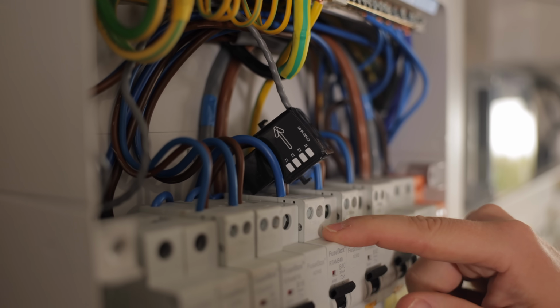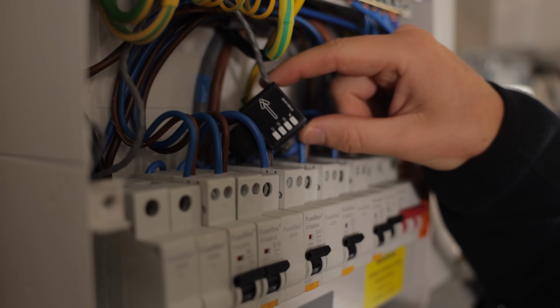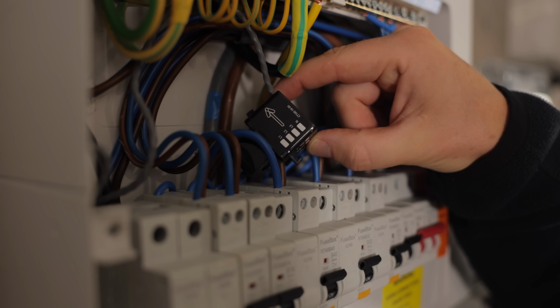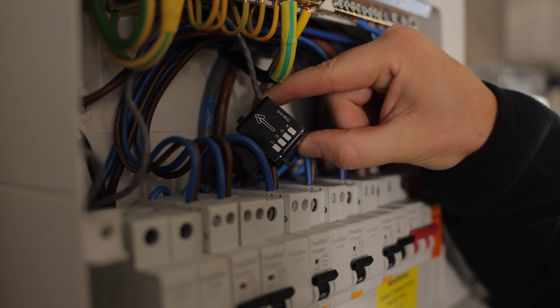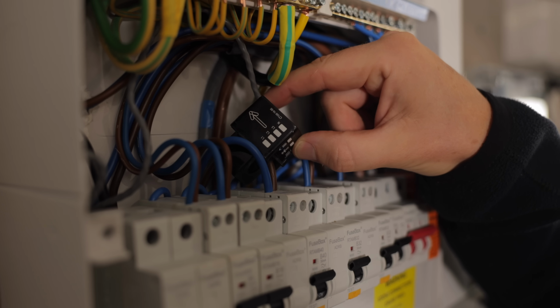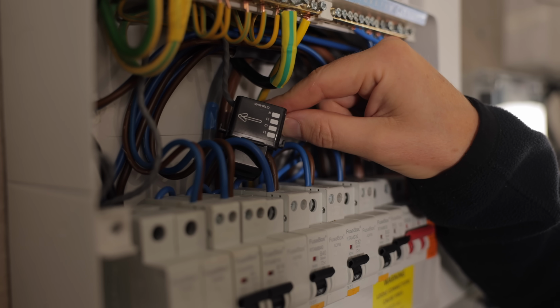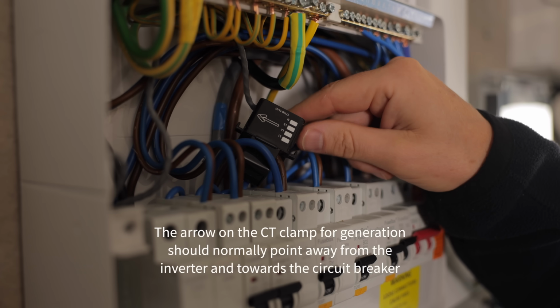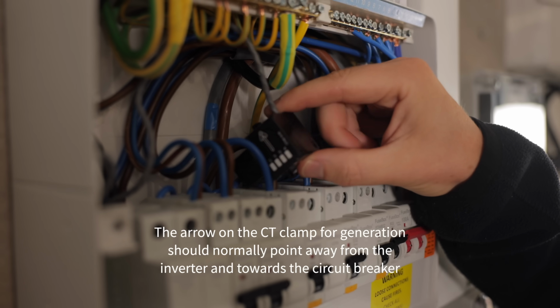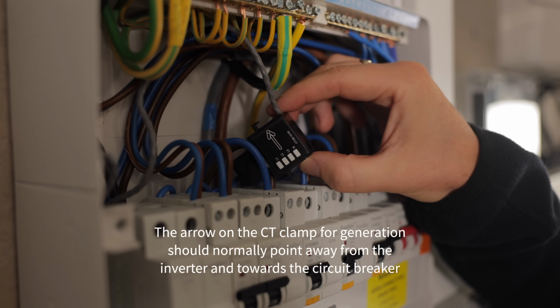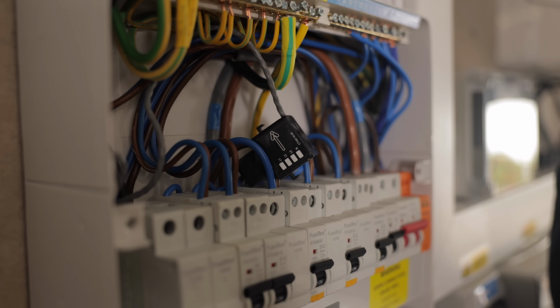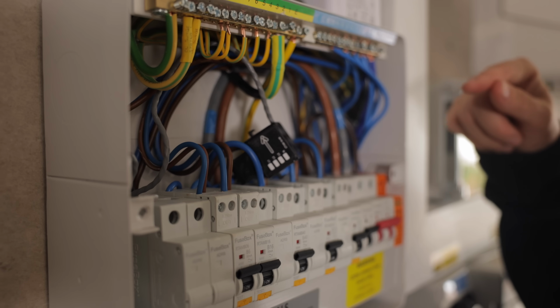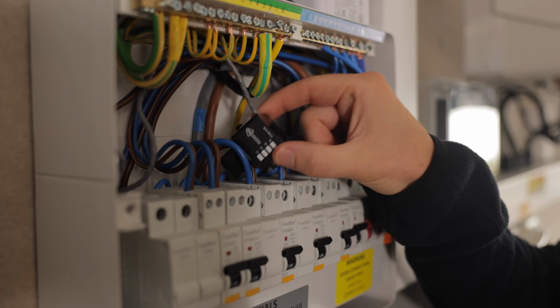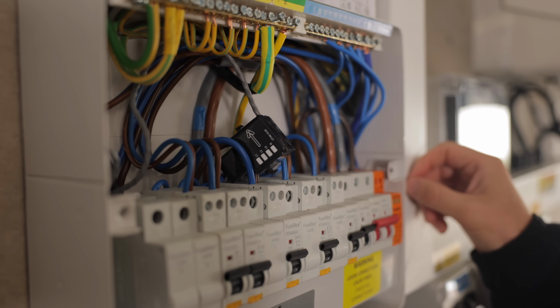On our existing solar circuit here, we've got a solar CT. This is for the MyEnergi system to read how much solar is being generated, and for you to gather data about your generation. You can get away without a solar CT with the MyEnergi system - it will just read import and export with the grid CT. However, we always like to add that additional CT just to gather that data.